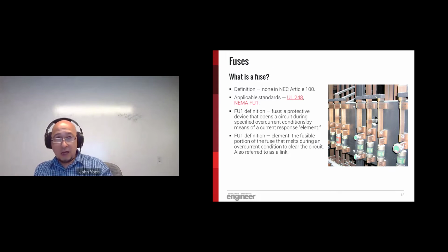Moving on to the next one, let's start with fuses. Fuses have been around for an extremely long time. The picture that you see in this particular slide is part of a 5,000 amp 208-volt live front switchboard from the 1940s. You can clearly identify the individual fuses, the fuse clips that they're seated in, everything else. Although it seems wildly obsolete and unsafe, this switchboard is actually still in operation. So even though fuses have been around for what seems like forever, there's no formal definition within the NEC for what a fuse is. As such, we have to rely on definitions from another source.